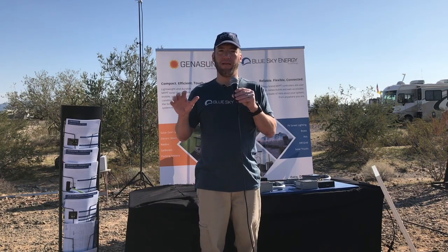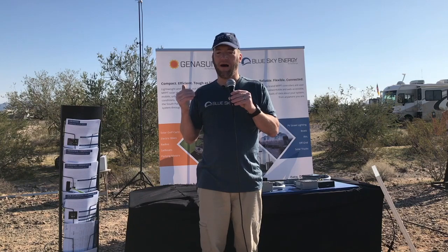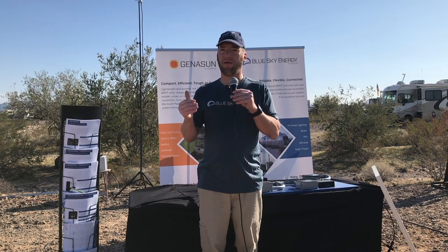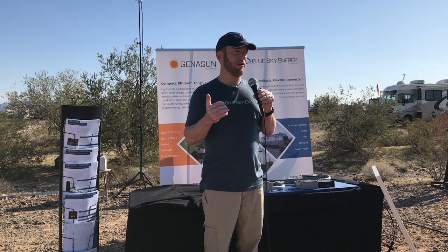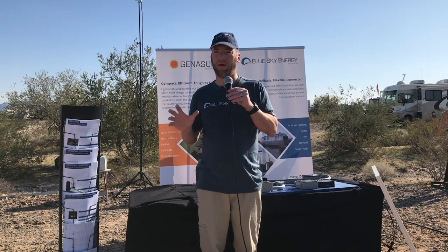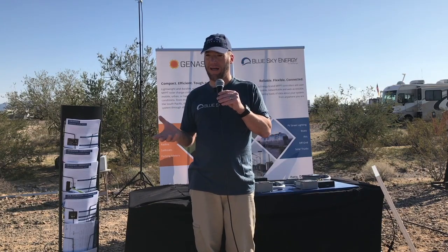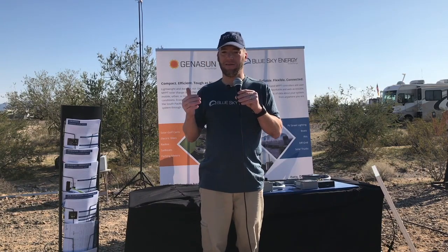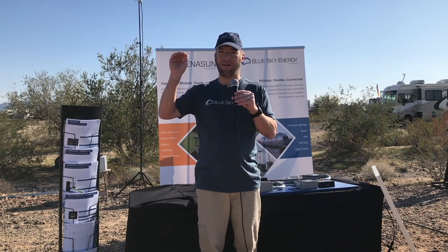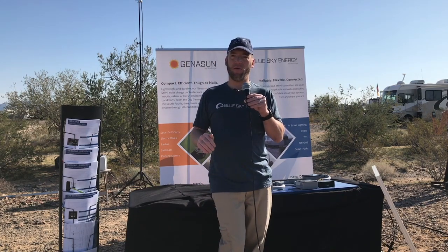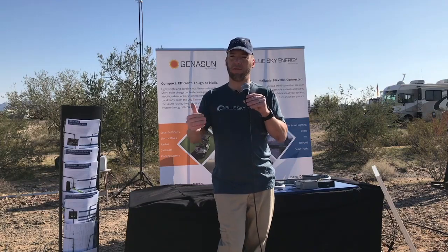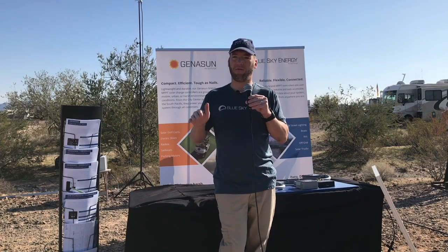Well, you need a charger with variable, programmable settings. The higher float voltage is specifically more necessary. If you traditionally have a charger that floats a battery at 13.2 and you can't alter that, you're going to have a hard time because your battery will discharge quite a bit before your PV starts taking up the load before the sun sets.